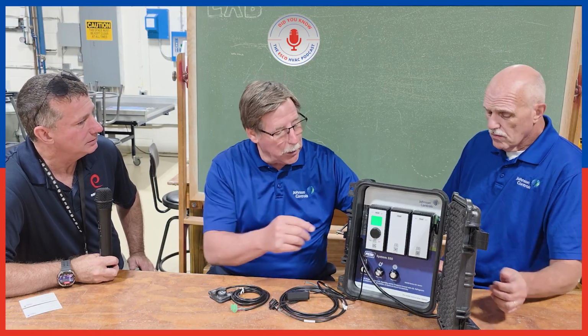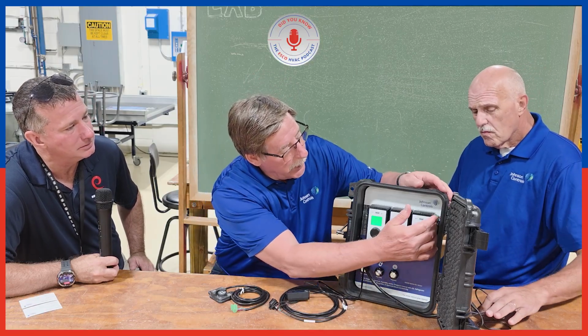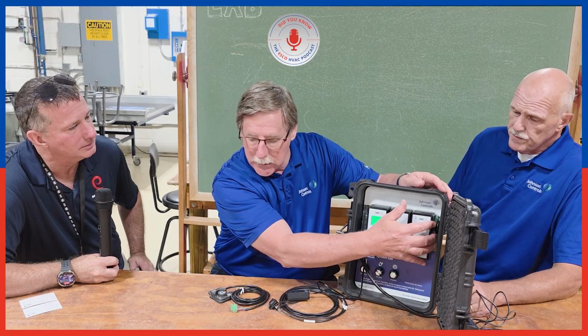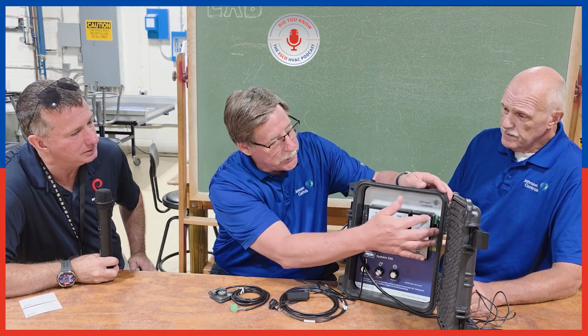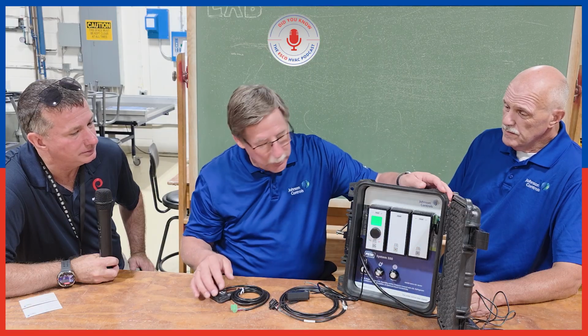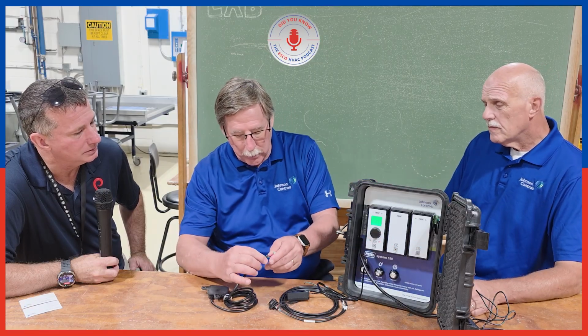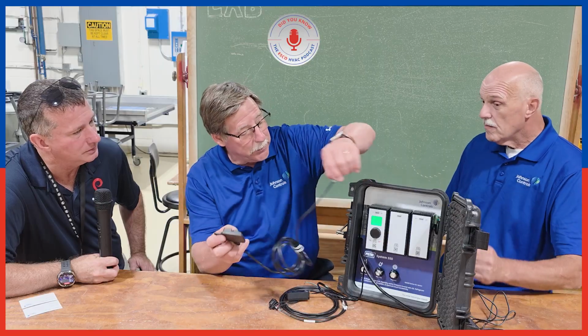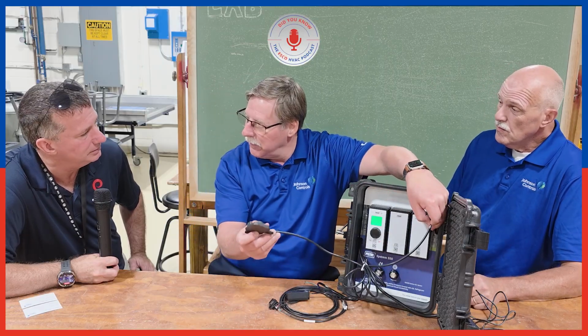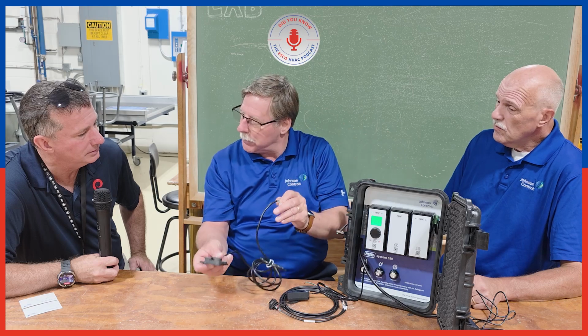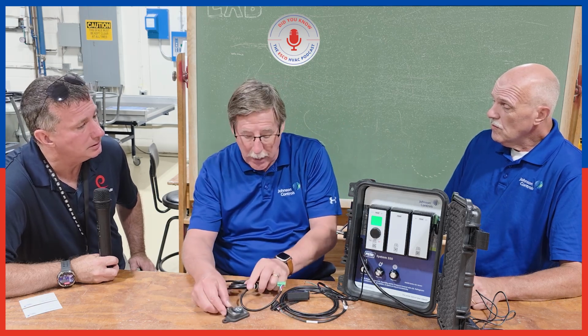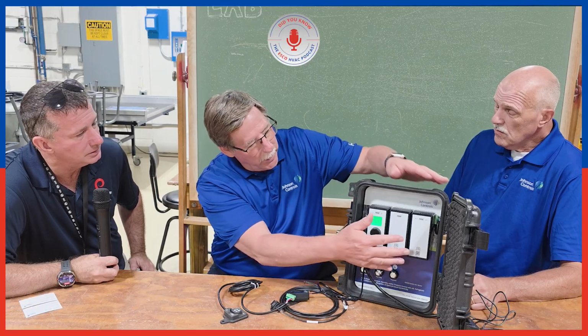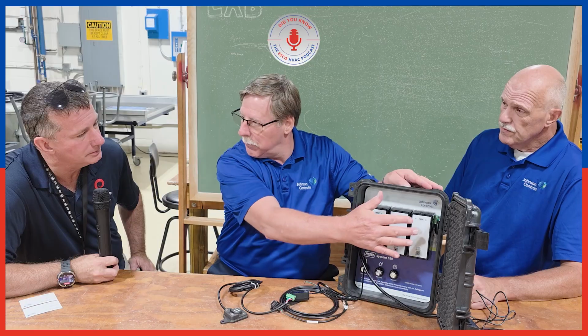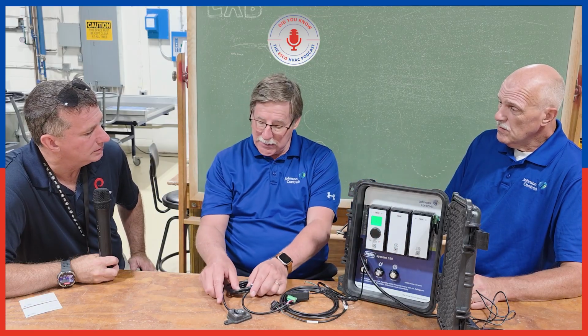It's a little difficult to see here, but on the right side of this last module, the expansion module - in this case a relay expansion module - you can see where this A2L sensor is wired in and connects into it. This has physical room for 2 sensors to be connected. If I need more physical space for more A2L sensors, we have a similar module called a junction wiring module that will accommodate up to 6 A2L sensors.